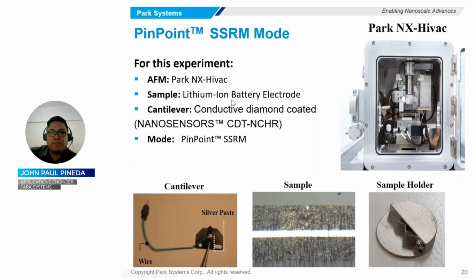So let's talk about the experimental setup. The instrument that we used in the experiment was the Park NX-Hivac. The sample we measured here was a cross-section area of a lithium battery electrode. The sample was mounted in a cross-section metal disc holder, and silver paste was applied underneath the sample to provide an electrical connection to the bias line. A conductive diamond coated probe from Nanosensors, model CDT NCHR, with a nominal force constant of 80 Newton per meter was used in the experiment.